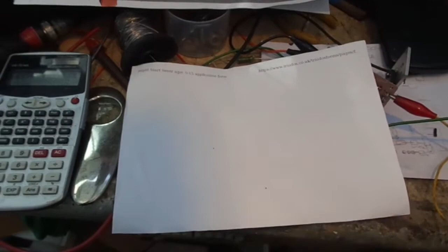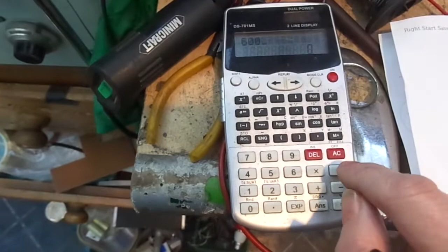So we've got 600 volts DC. Well, we can't use that DC winding figure and times it by the current, because that's wrong. The AC that comes off the power transformer will be lower. So what we need is to divide that 600 volts. We've got 600. Now you can divide it by 1.414, which is the correct...